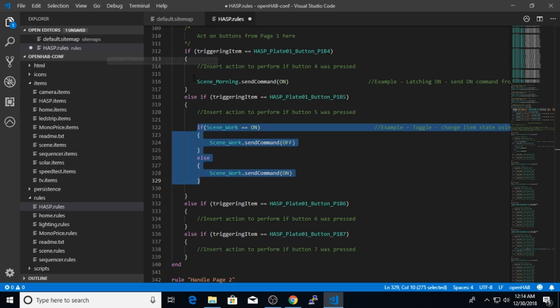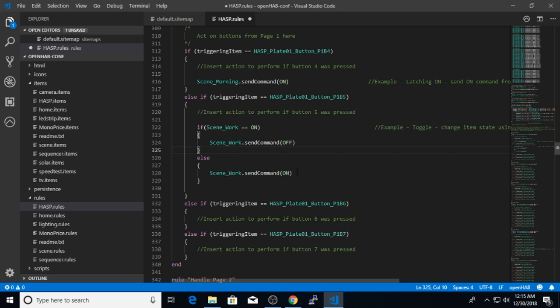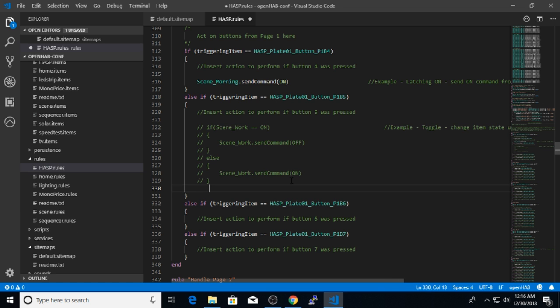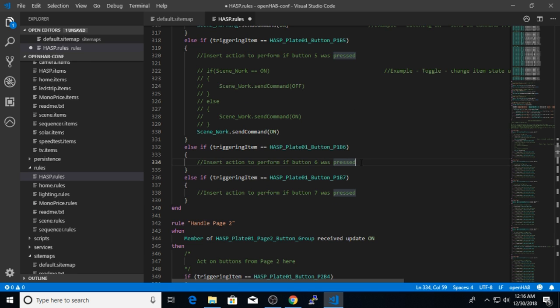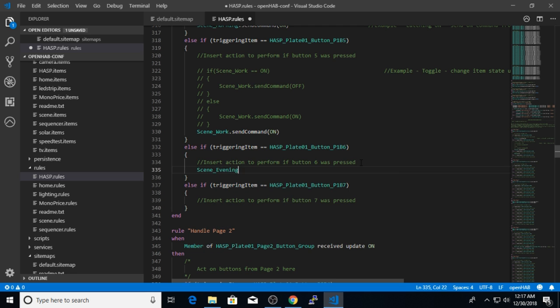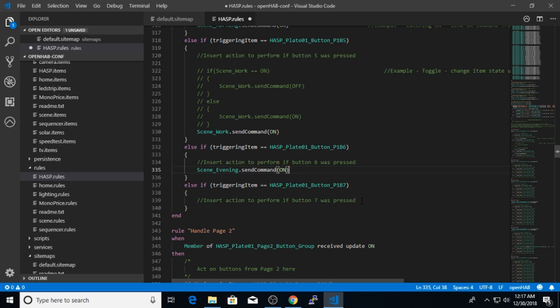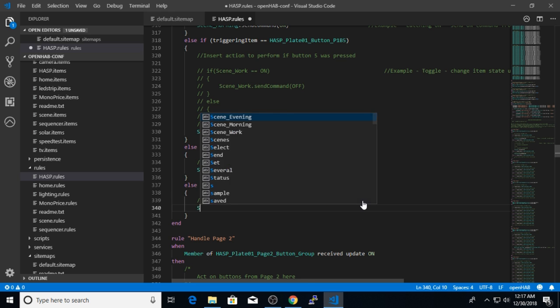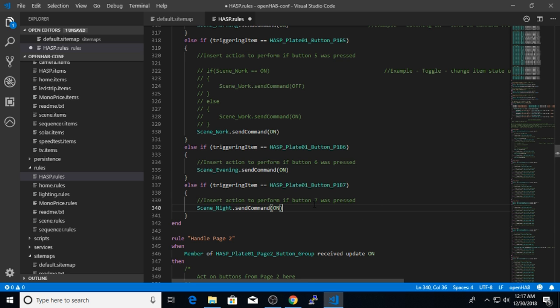So with the toggle logic, if the button labeled work scene has been pressed on the HASP, I will first check the state of that work scene item. If it's on, I will turn it off. And if it's off, I will turn it back on. So this logic will handle that toggling action. But in this case, since I'm working with scenes, I simply want to send the on command when that push button is pressed. The third button on screen one is the evening scene. So I will send the on command to the evening scene item. And the last one is the night scene.